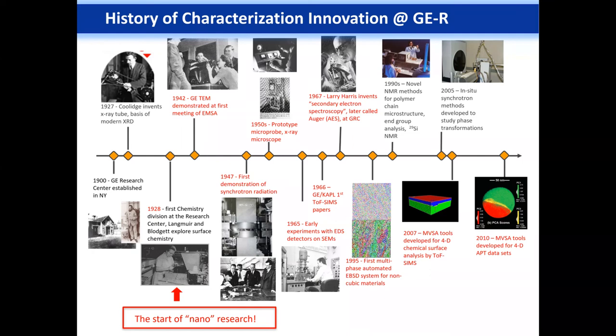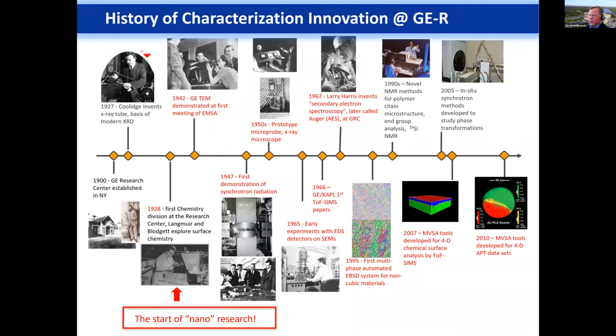Another question: for 10- to 30-nanometer or even smaller particles on the surface, does AES have a chance to analyze them, or are there other techniques you'd recommend? For particles that small we would usually start with Auger. When selecting the best tool, consider the spot size needed and the composition query. They're probably most interested in major constituent composition rather than trace species. With SIMS and newer instruments you'd be able to get some useful information, but it highly depends on the material, and there would be a probability that images would be a bit blurred.